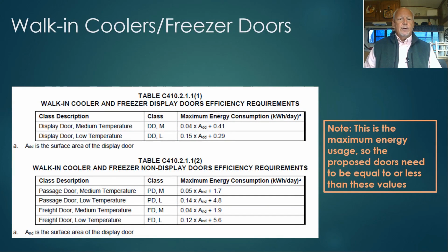So I've thrown out some tables here. The standards begin with the requirements for walk-in cooler and freezer doors. So there's a new table. If you have a walk-in cooler or freezer less than 3,000 square feet, then your cooler and freezer doors have to meet these minimum standards. Now, if it's a display door and a medium temperature door, it has to meet a maximum energy consumption value, in kilowatt hours per day, based on the area of the door and the calculation in the table. Being that this is a federal standard, this data should be labeled on the door, or you should be able to get this data directly from the manufacturer.